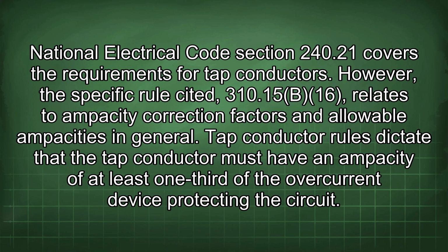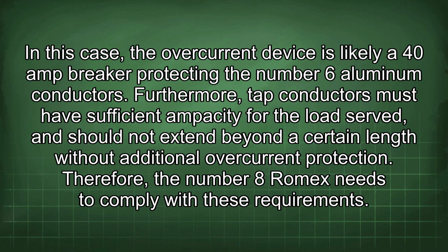Tap conductor rules dictate that the tap conductor must have an ampacity of at least 1/3 of the overcurrent device protecting the circuit. In this case, the overcurrent device is likely a 40 amp breaker protecting the number 6 aluminum conductors. Furthermore, tap conductors must have sufficient ampacity for the load served and should not extend beyond a certain length without additional overcurrent protection. Therefore, the number 8 Romex needs to comply with these requirements.